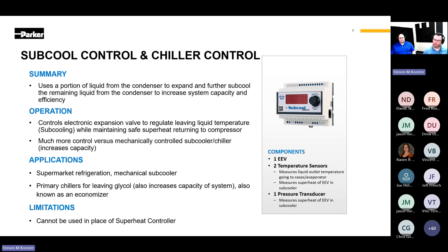The subcool and chiller control both control to liquid out temperature and monitor superheat. They will take over superheat control if the superheat drops too low. The main difference between these two controls is the cutoff temperature configuration. The subcool control uses an offset — for example, if you have a 50-degree liquid set point and set the subcooler off temperature differential to 30, that 30-degree offset will turn the subcool controller off at 20 degrees. While this is fine for a subcooler application, a chiller could have problems running the liquid temp out that low, and the chiller control has a hard, low temperature cutoff.